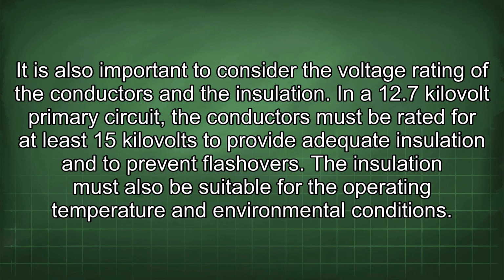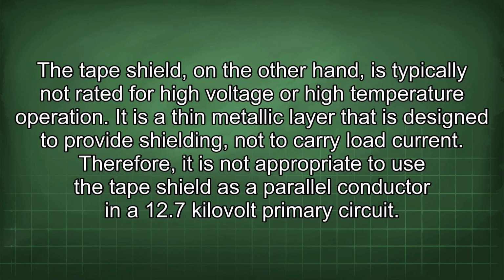The insulation must also be suitable for the operating temperature and environmental conditions. The tape shield, on the other hand, is typically not rated for high voltage or high temperature operation. It is a thin metallic layer that is designed to provide shielding, not to carry load current. Therefore, it is not appropriate to use the tape shield as a parallel conductor in a 12.7 kilovolt primary circuit.